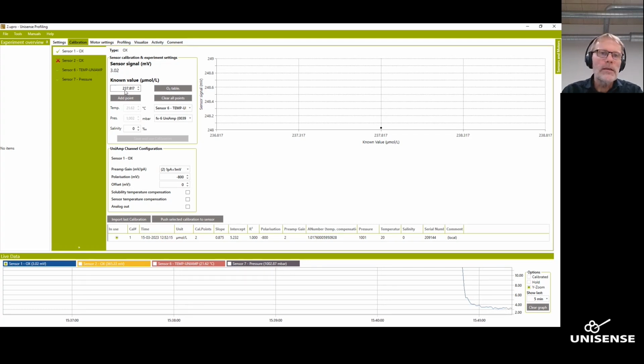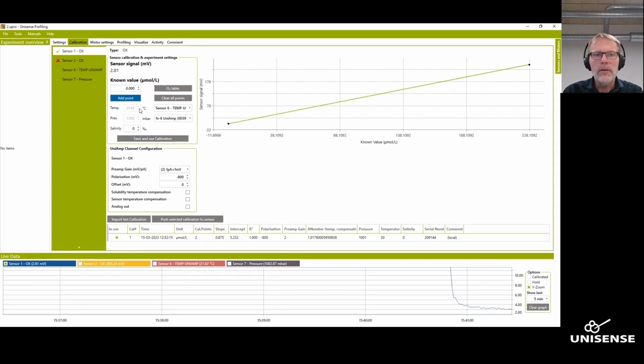Then I will change the known value here to 0 because it's anoxic, and then just add point. Once I've done that, I just need to click the Save and Use Calibration, and then the sensor is calibrated. See, now a second calibration showed up here, and this is the one that is in use. It shows the timestamp and everything.